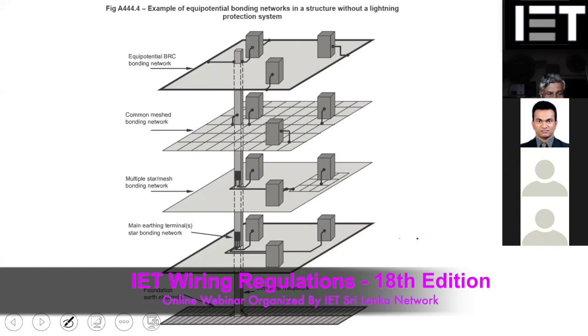One example: you can refer to the standard, which gives a very good description of equipotential bonding. Even in a multi-story building, you can have structural earthing and foundation earthing, and everything will be connected together. No different earths. You don't want to run separate earths, but rather connect to a common earthing arrangement, so that everywhere you get the same potential. That is the basic concept, and it will minimize electromagnetic interference as well. In order to minimize the interference, you have to have equipotential bonding. That is the requirement of the new regulation.